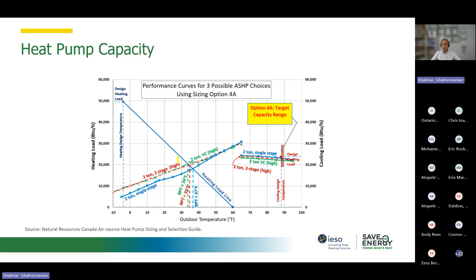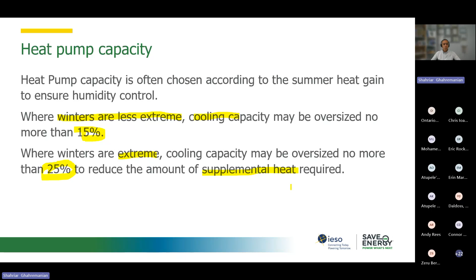So basically, in regions where the winters are less extreme, the cooling capacity will be oversized by 15%. So for areas like Windsor and Toronto, they are not very extremely cold in the winter season, so the heat pump can be oversized by 15% on the cooling side. But if we go to the northern part of Ontario, where the winters can become extreme, then we are allowed to oversize the cooling by 25%. So it's okay. But again, in those cases, most of the time, we need supplemental heat to be provided for those extreme cold days actually.